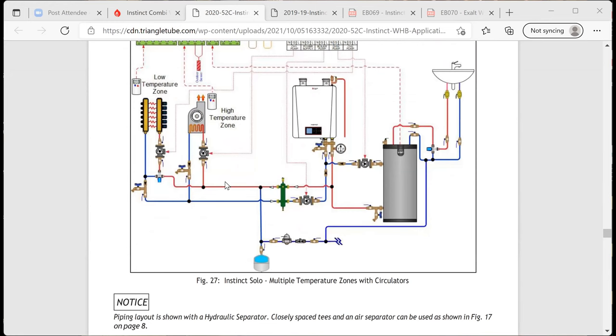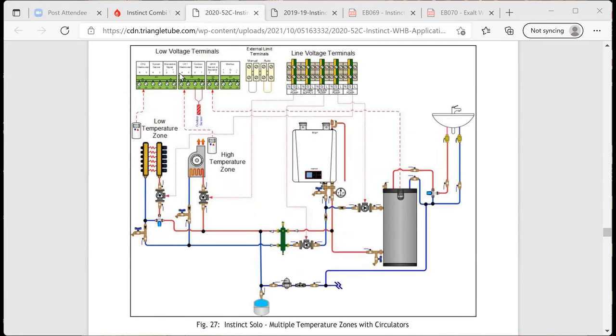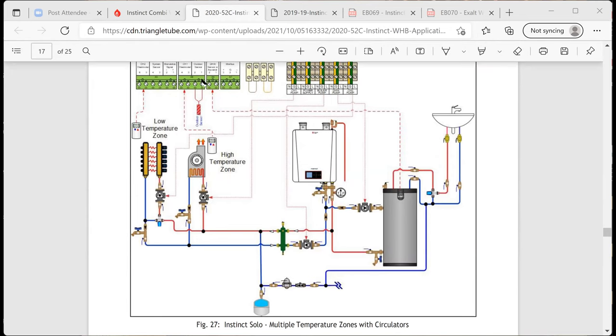And this one's showing, going back to the CH1 and CH2 differential curves, we're using a high temp fan coil, say 180 going through this when CH1 calls, and then when CH2 calls, it's running at a low temp, but we still need that mixing valve in there to mix that down and protect it.